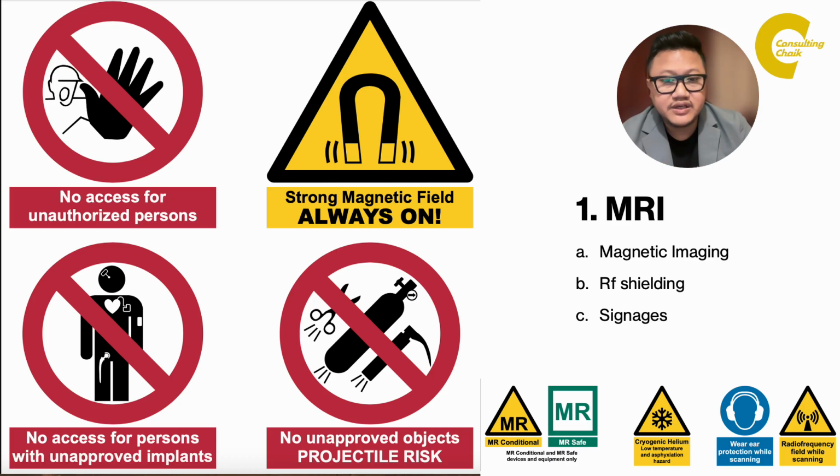You will be able to see there were many metallic objects which got stuck in the MRI, and in order to remove that, we have to remove the whole helium, and to refill the helium costs lakhs of rupees, and a lot of headache, and several loss of opportunity of patients. So it is very important that the staff always stays vigilant about these things.